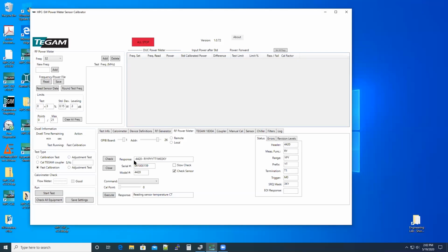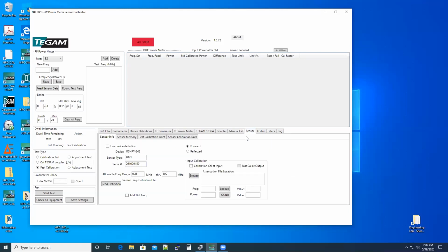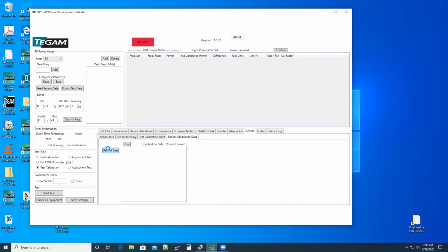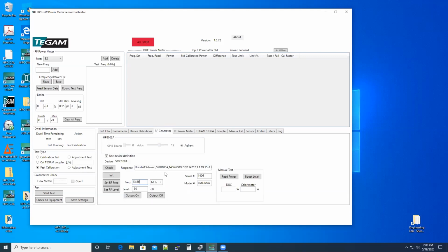I get some answers that are very low because there's no power on right now. I'll check the RF power meter. It's been checked, it's connected. It read a serial number from the sensor. You can check the sensor, it's a 4021. Everything's good to go. I can read the sensor calibration data out of it, and make sure it has all the points we need in it. Sometimes this takes a second to do. So this sensor is calibrated from 1.8 megahertz to 32 megahertz. What else do I need to look at? I've got my generator connected. It's a Rohde & Schwarz. I've got the drivers for it loaded.